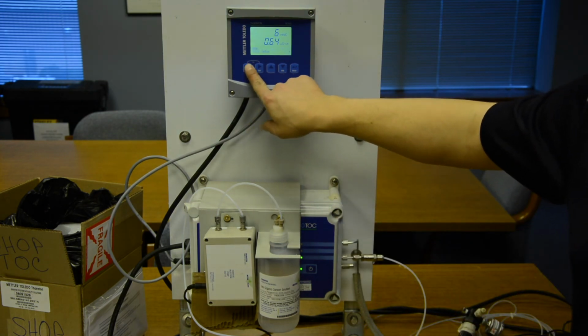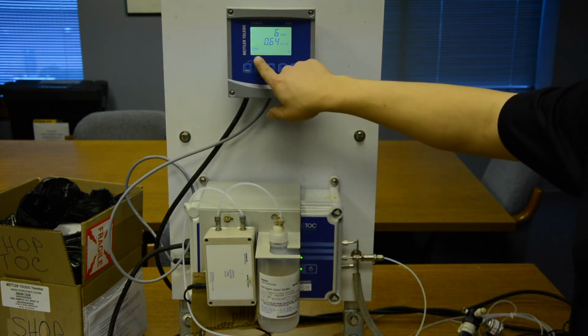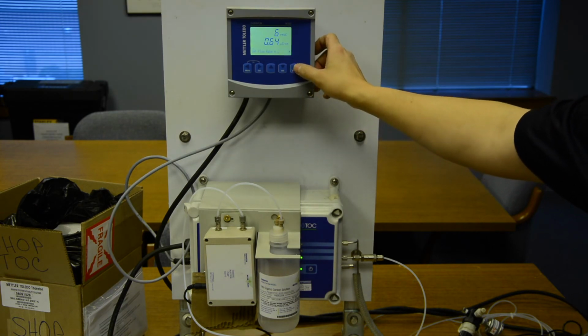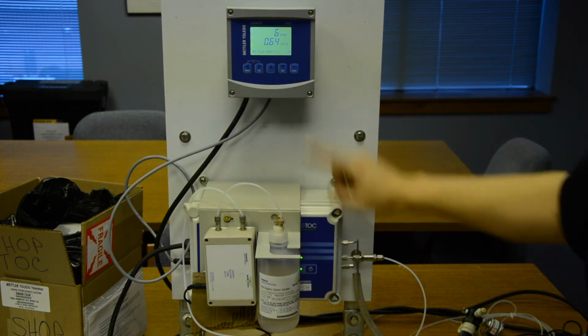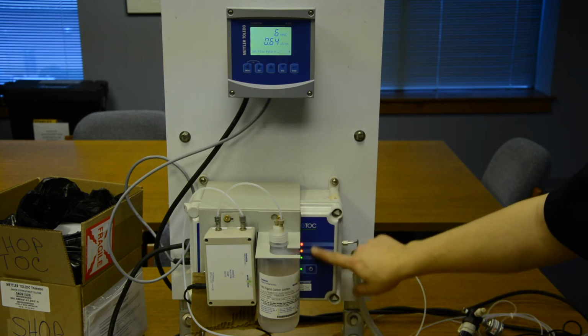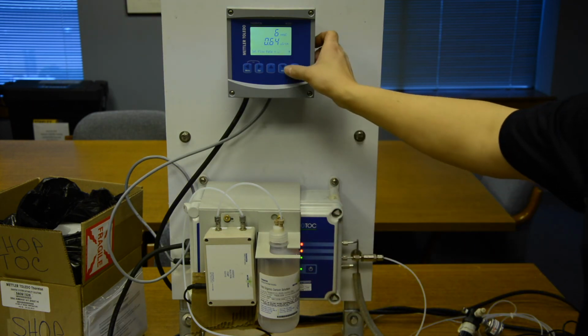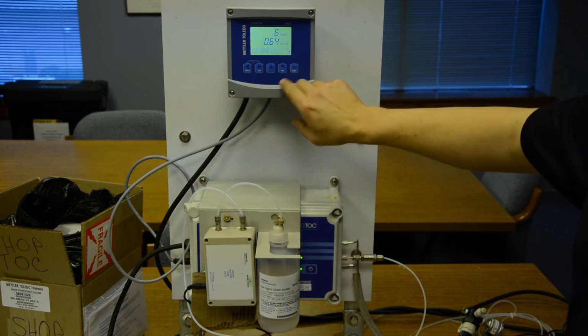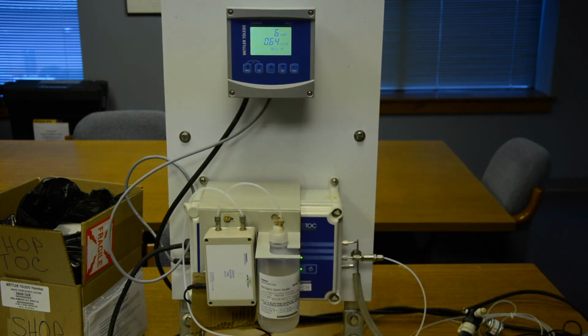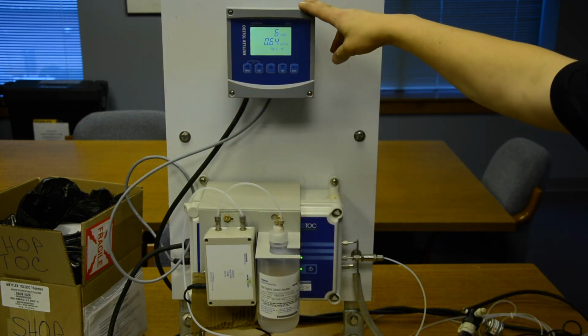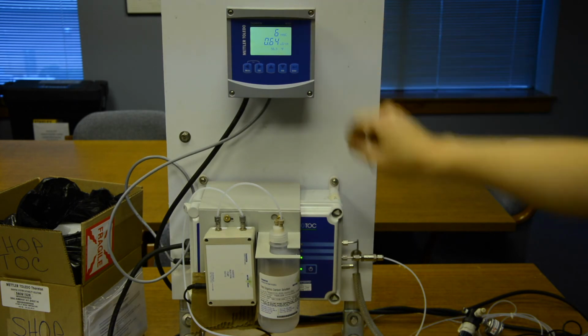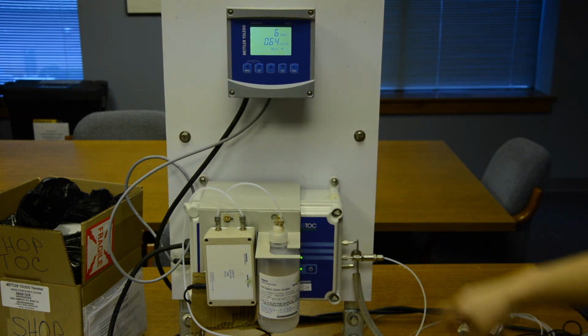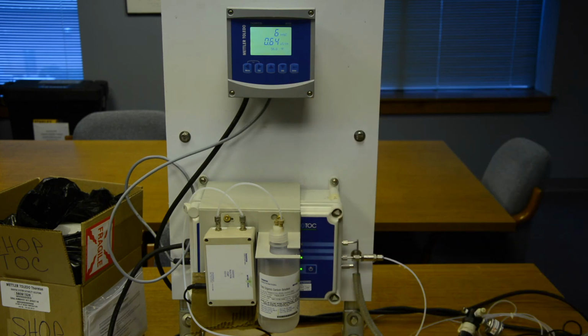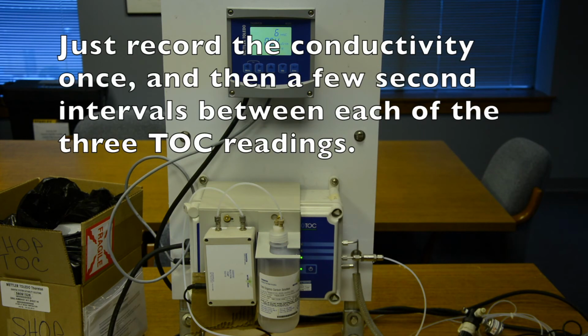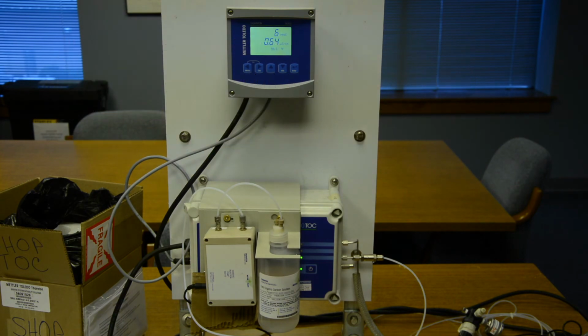Let's go into your menu, scroll to set flow rate, hit enter, go up to on, and then it'll show your flow rate, so you can see our flow rate is correct. Go back down to off, and you can exit that menu. So you can see right now that our first standard solution, the reagent water, is reading 6 parts per billion, and we're reading it at 0.64 microsiemens. So our first recording will be 6 parts per billion at 0.64 microsiemens per centimeter.